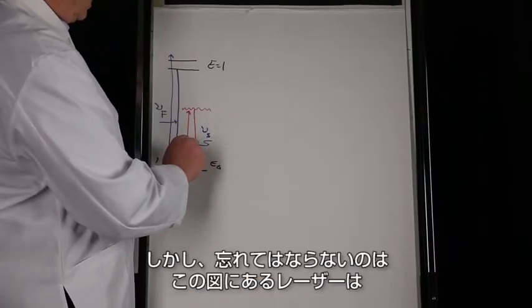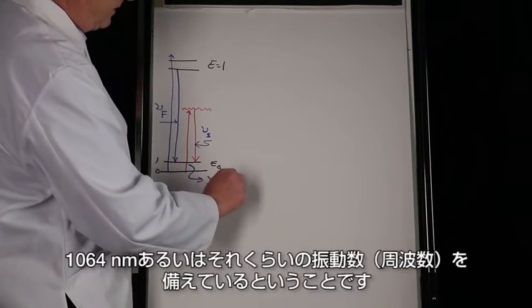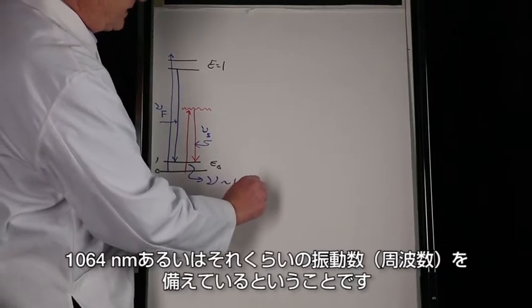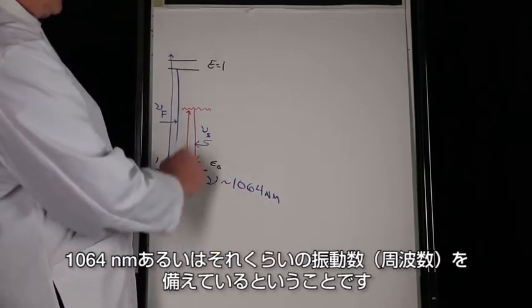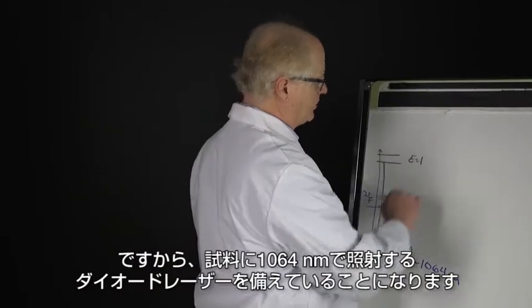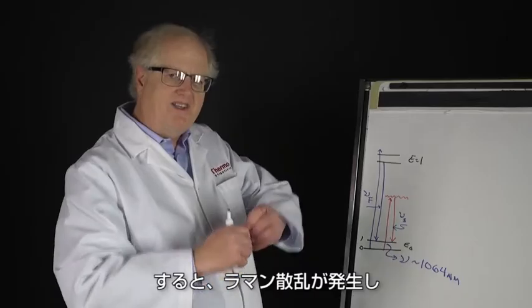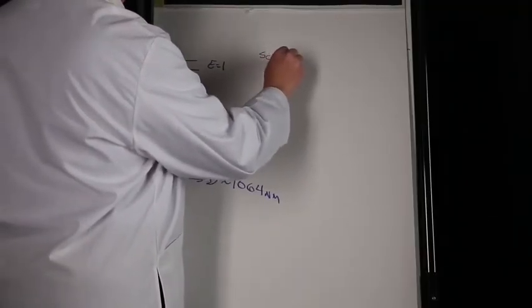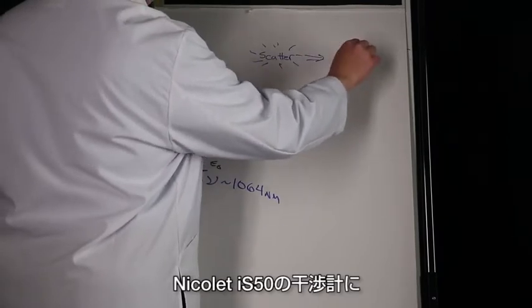This laser now has a frequency of, or it is, 1064 nanometers. You have a diode laser that shines onto the sample at 1064, then the Raman scatter comes off and that Raman scatter is treated as if it was a source and that's fed right into the interferometer.